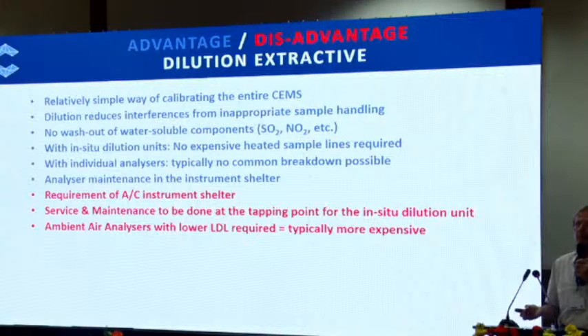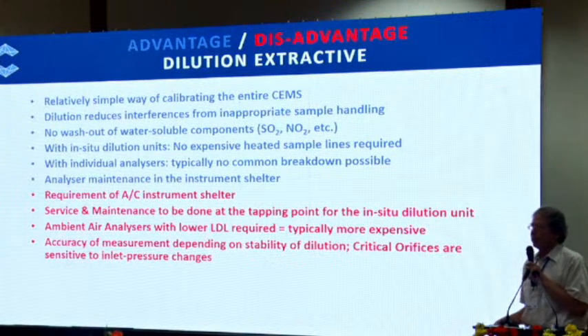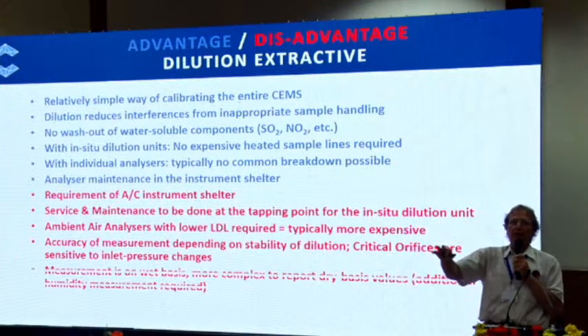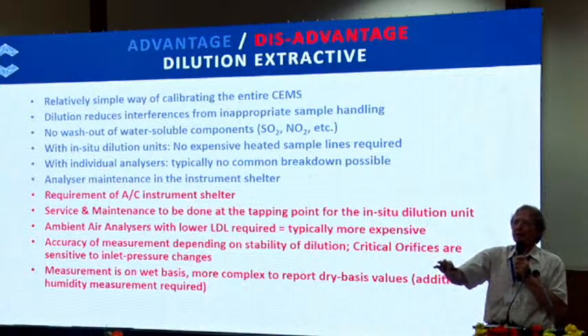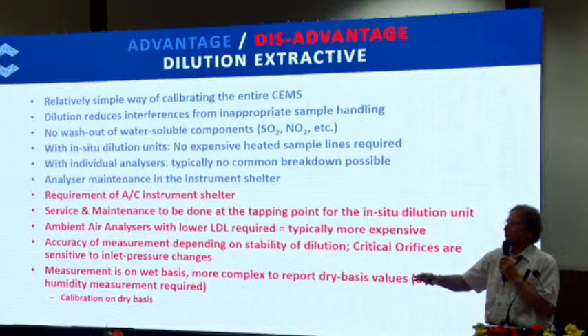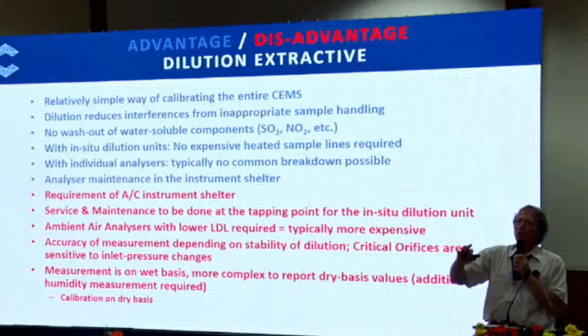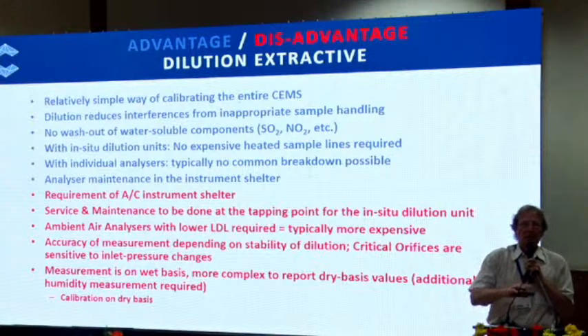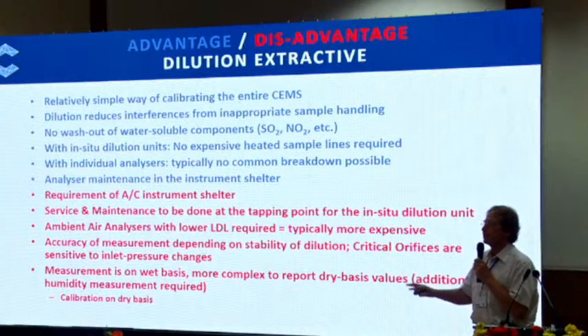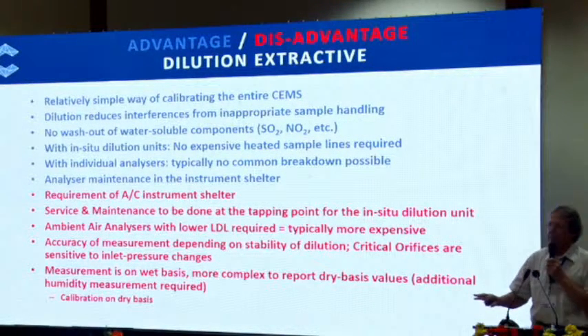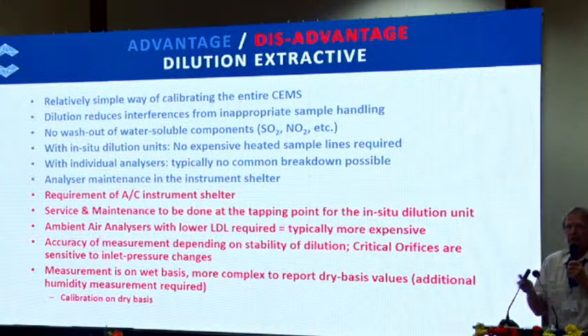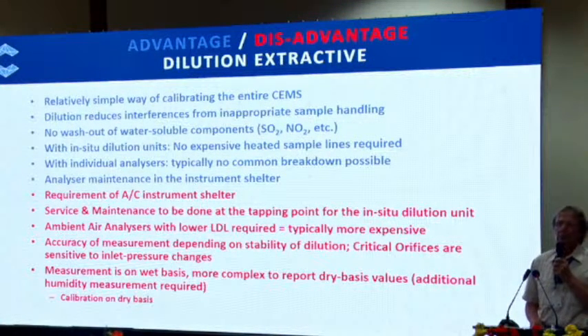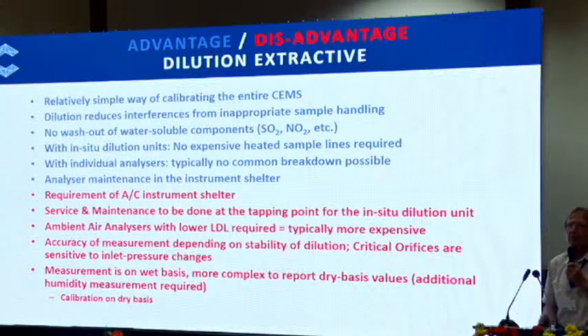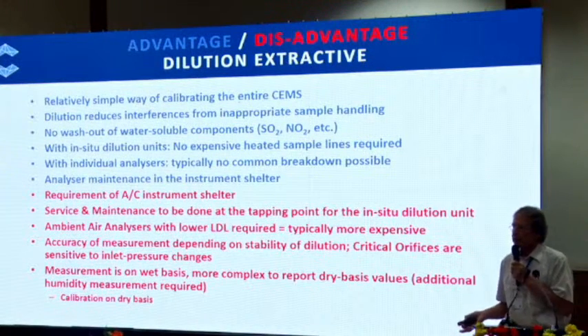Okay, my dilution probe service maintenance is at the tapping point. But now I'm not only diluting my water, I'm also diluting the concentration. That means my analyzers have to be more sensitive. Most likely I have to go to air quality concentration-based analyzers, and they're more expensive than the typical CEMS analyzers. So that can be a significant disadvantage, specifically when it comes to the investment cost. If my dilution is not stable, of course, then I have problems with the accuracy.